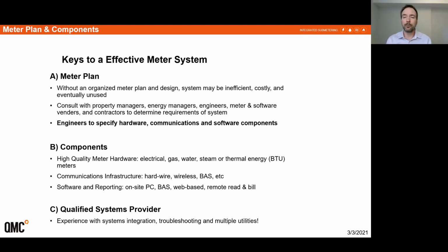One thing we've found historically is a challenge with a lot of consultants: bridging the gap between the electrical side and the mechanical side, because almost all of the systems we deploy now have multiple utilities in them. You need integration between electrical metering, which has historically been the majority of metering done, along with new mechanical systems like BTU, water, or gas, plus the entire communications infrastructure. So our specification is actually a multi-utility specification, and whether it sits on the electrical side or the mechanical side usually depends on which has more metering. But we will make that available to your subscribers.